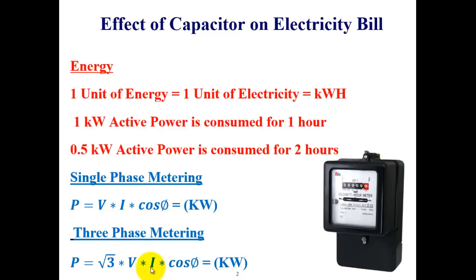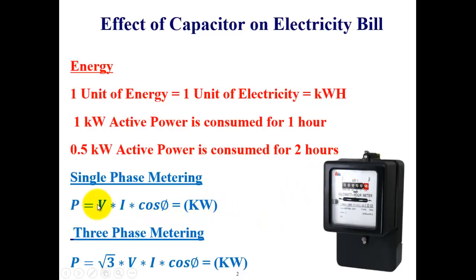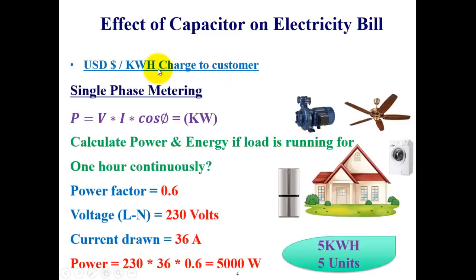Once voltage and current are measured, the last quantity is cos phi — the power factor. Since both voltage and current are AC quantities, this electronic device can compute the angle between them, and taking the cosine of that angle gives the power factor. By multiplying these three quantities, the meter calculates active power in kilowatts, and multiplying by time gives the total energy consumed.